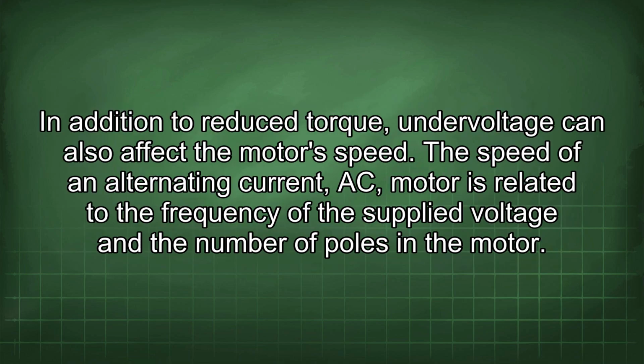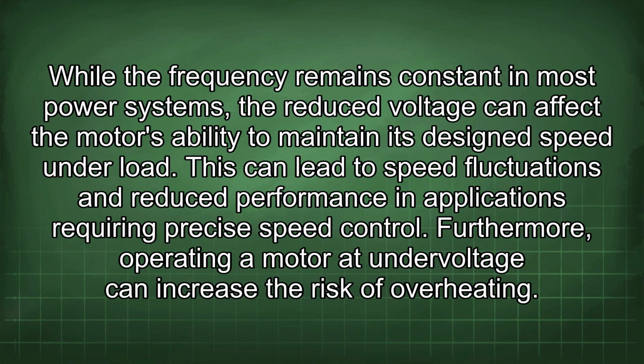In addition to reduced torque, undervoltage can also affect the motor's speed. The speed of an alternating current (AC) motor is related to the frequency of the supply voltage and the number of poles in the motor. While the frequency remains constant in most power systems, the reduced voltage can affect the motor's ability to maintain its design speed under load. This can lead to speed fluctuations and reduced performance in applications requiring precise speed control.